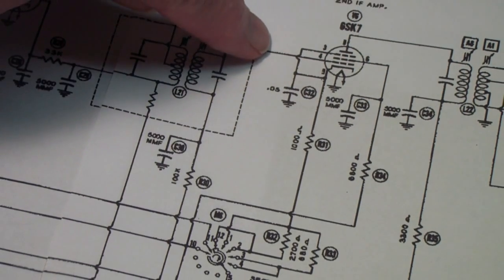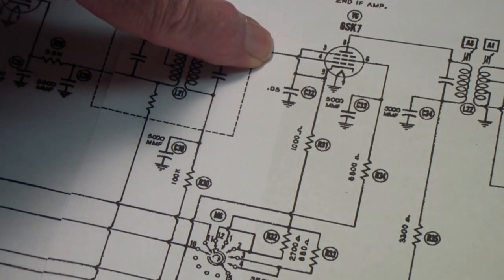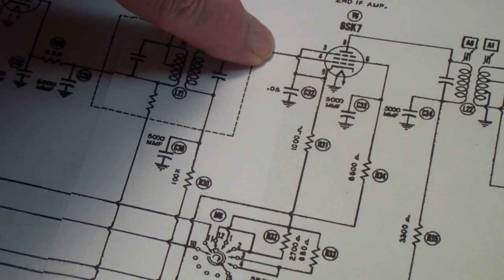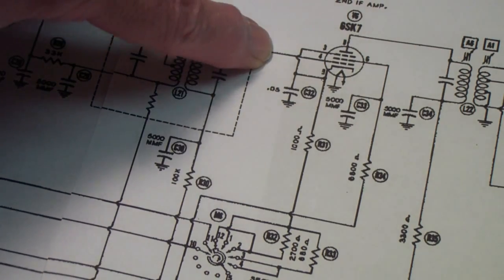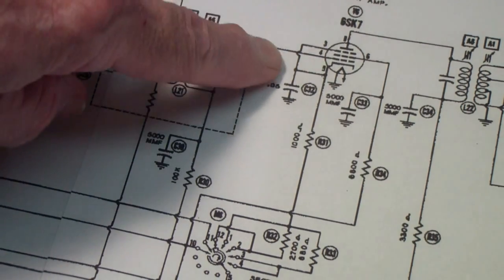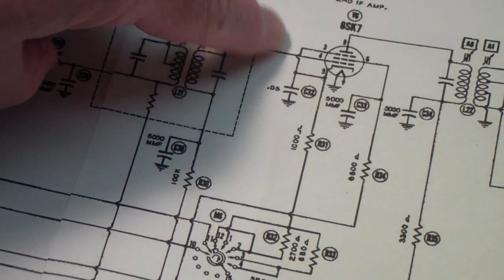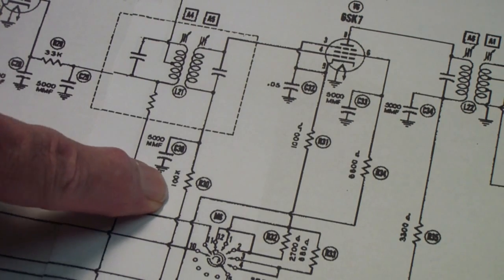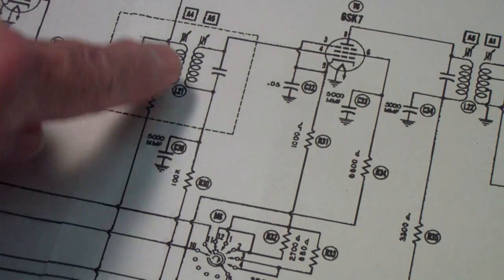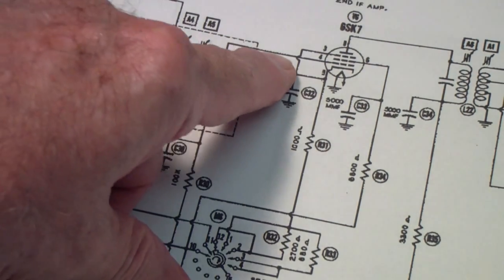Using my earlier example of a 20,000 ohm per volt meter on a 10 volt scale, if you try to measure that voltage, you're basically putting a 200K resistor in parallel with a 100K resistor, and that's going to substantially change the grid voltage.